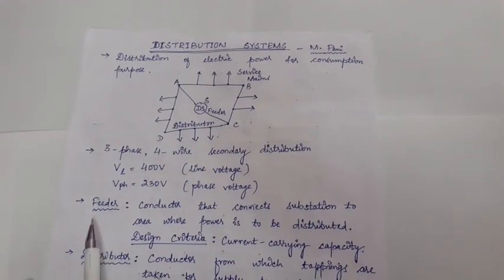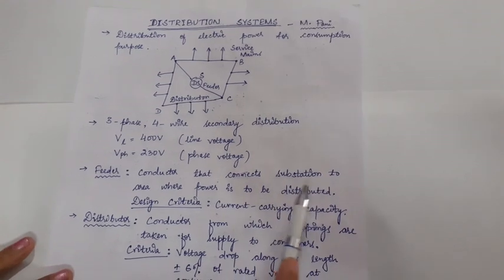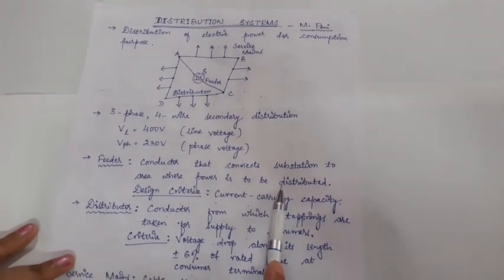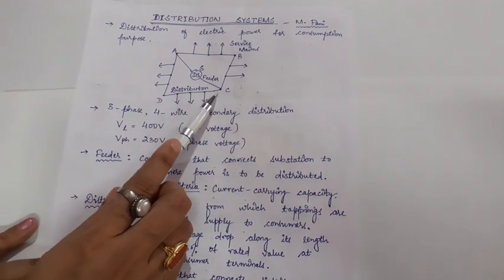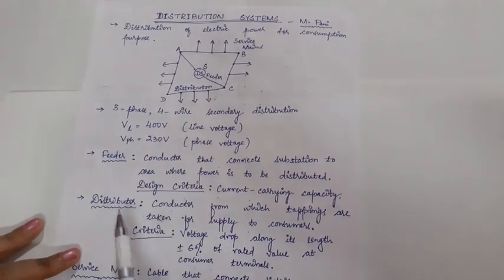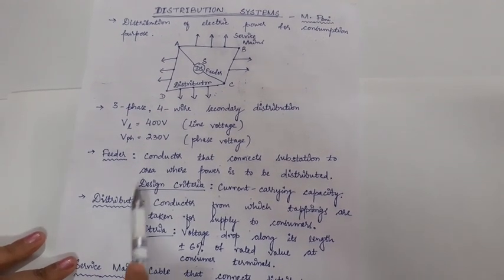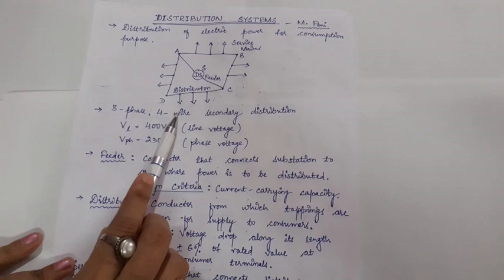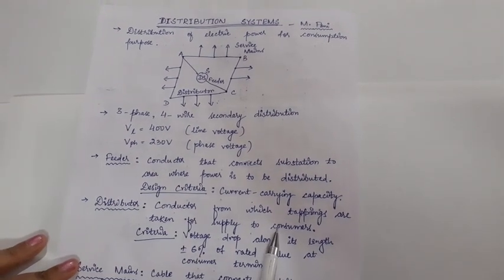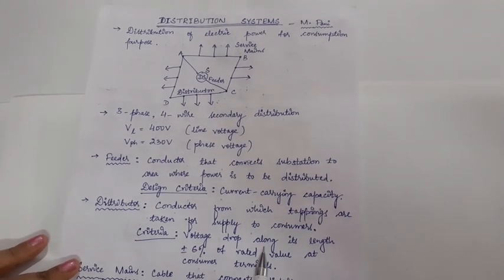The feeder is a conductor that connects the substation to the area where power is to be distributed. The design criteria for a feeder is the current carrying capacity. The distributor is the conductor from which tappings are taken for supply to the consumers. The design criteria considered for a distributor is the voltage drop along its length.